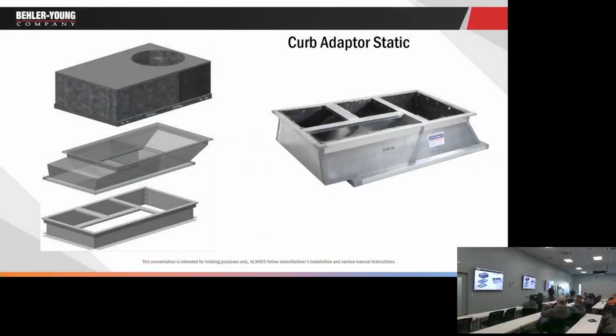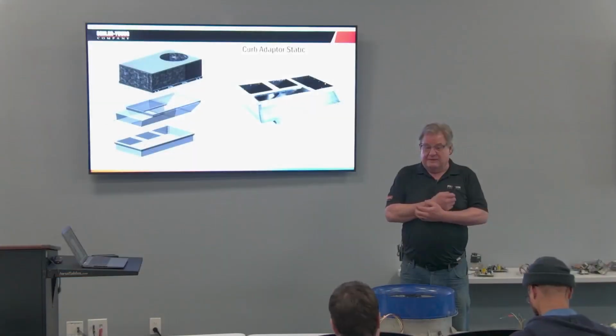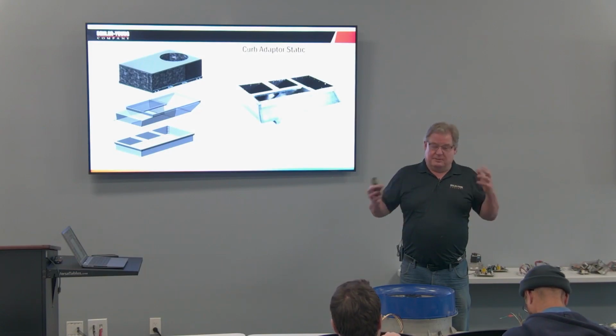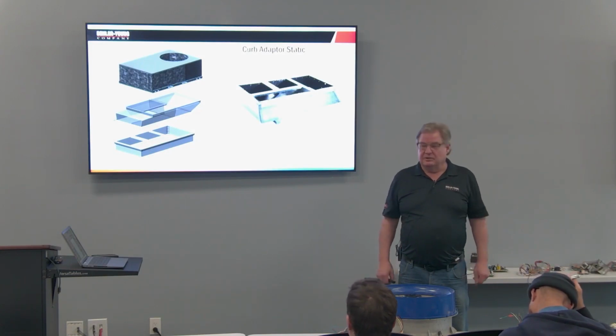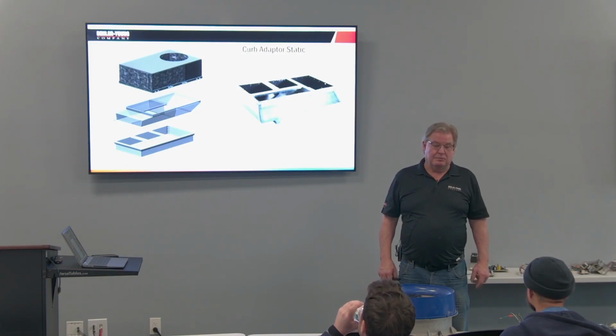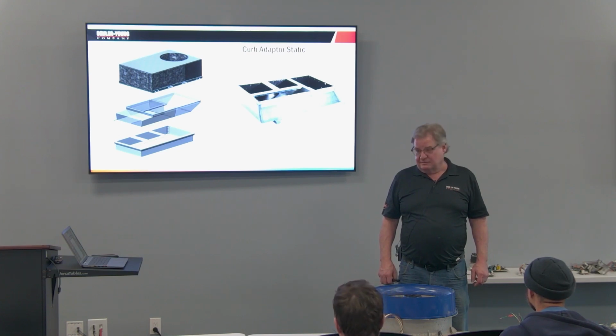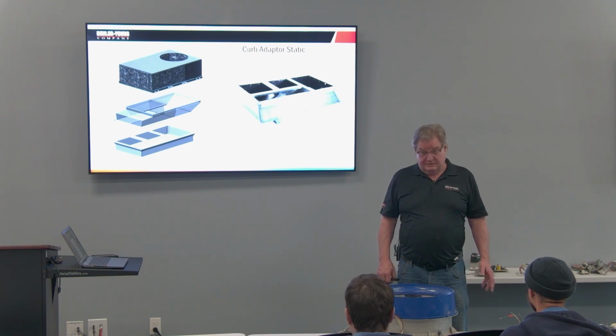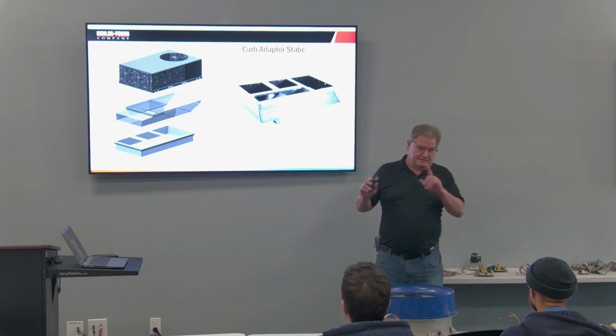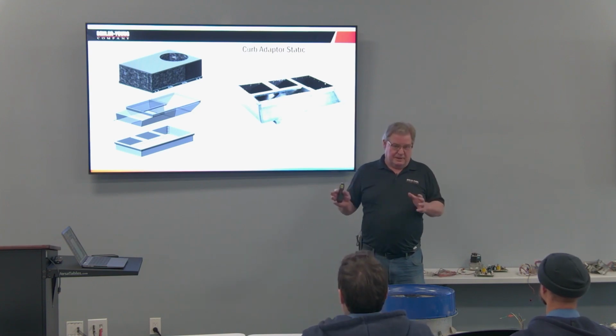Curb adapters. Okay. When you get the curb adapter, there should be a document that tells you what the static is. The engineers figured it out for you. I had a curb adapter up north. We had a medium static unit on it, the old belt drive, and kept tripping limits. We couldn't get airflow. Well, we find out the curb adapter had 0.8 inches of static. That's a lot. Okay, the average commercial duct system is designed at about 1 inch, residential about 0.5.